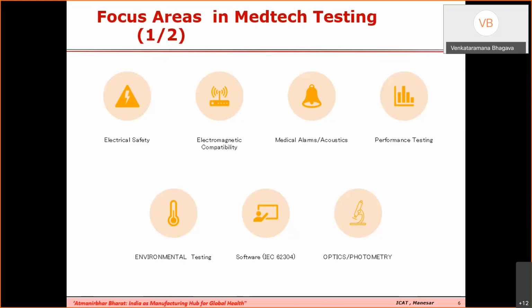Okay, we'll move ahead. The next category of test is the environmental test. In environmental testing, the device is put under a lot of stress conditions, let's say humidity, temperature, torque, vibration, and so on. Let's say if a device is to be used in an ambulance, it has to undergo certain vibration tests which will simulate the conditions in an ambulance. So the enclosure has to be a bit rigid and so on.